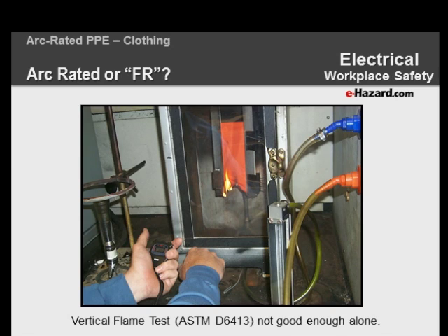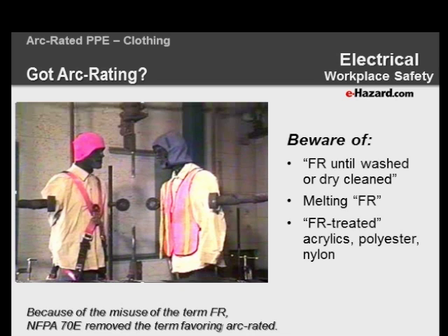In clothing, you want to meet ASTM F1506. You don't want the D6413, or the old federal test method people use, or NFPA 701, which is actually a curtain standard. These are deceptive companies in some cases, or companies that are just not very knowledgeable about FR. They're frequently imported—almost every case, they're imported. There's good imported stuff, there's bad imported stuff. Always check the labels and make sure something meets the standard. If you have any question, if it's half the price of everybody else, there's probably a problem. In some cases it's actually deceptive and they're not really selling you what they say they're selling you, and we've seen this a few times.